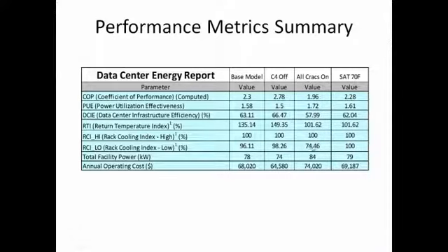In fact, it was running a little cold. So then the final thing we did was to increase supply air temp, which went to 2.28, and that gave us a PUE of 1.6, just about where we started. But now we have a good relationship between air coming out of the cooling units compared to air being required by the racks, and also the temperatures are in line as well.